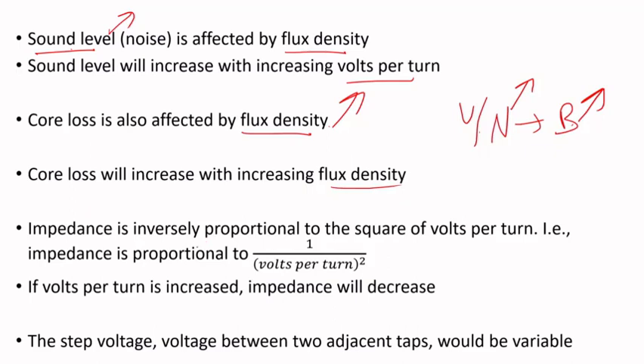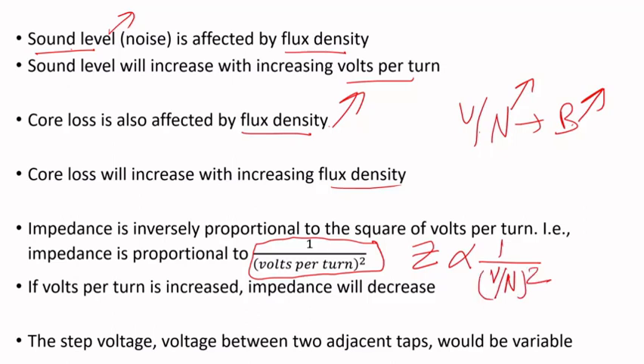Impedance is inversely proportional to the square of volts per turn — the transformer impedance is proportional to 1 over (volts per turn)². So if volts per turn increases, impedance will decrease significantly. This is important to keep in mind especially for paralleling transformers and other applications. Also, as you change taps with an LTC, you'll have a step voltage between adjacent taps, so that step voltage will also be variable.